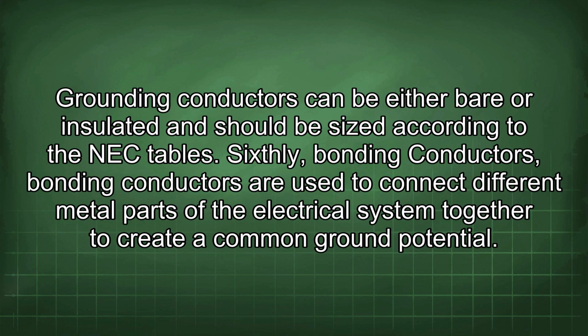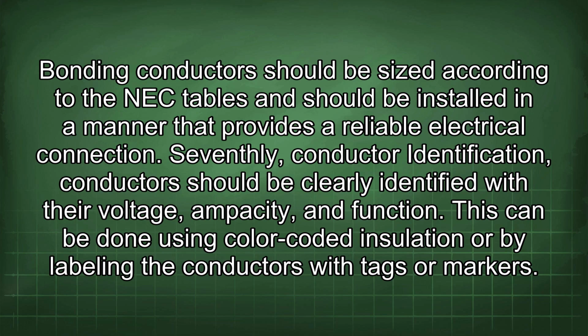Sixthly, bonding conductors. Bonding conductors are used to connect different metal parts of the electrical system together to create a common ground potential. Bonding conductors should be sized according to the NEC tables and should be installed in a manner that provides a reliable electrical connection. Seventhly, conductor identification. Conductors should be clearly identified with their voltage, ampacity, and function. This can be done using color-coded insulation or by labeling the conductors with tags or markers.